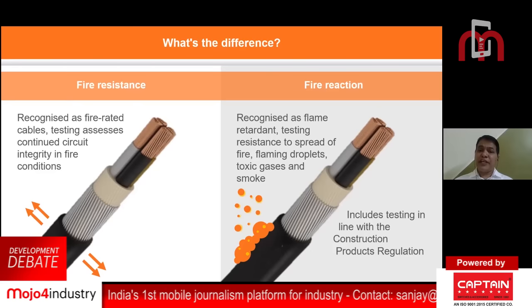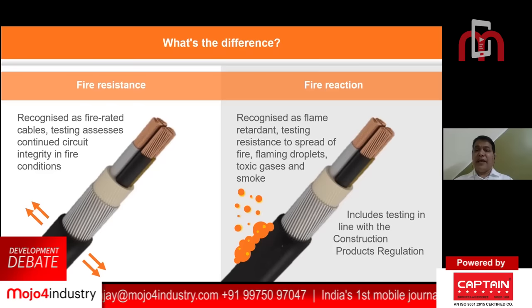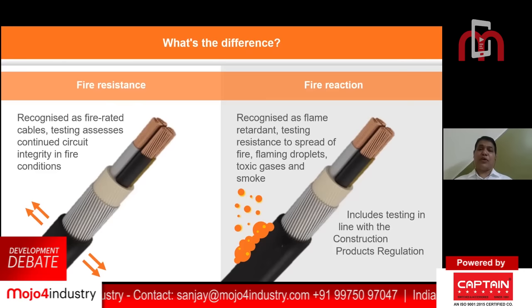When it comes to fire reaction cable, I would say all cables used within a building should have fire reaction properties. That is what the European Union and UK have done. Any cable inside a building needs to pass minimum properties—it could be smoke, flame propagation, or flaming droplets because of the melting of the sheath, insulation, or sheathing materials.